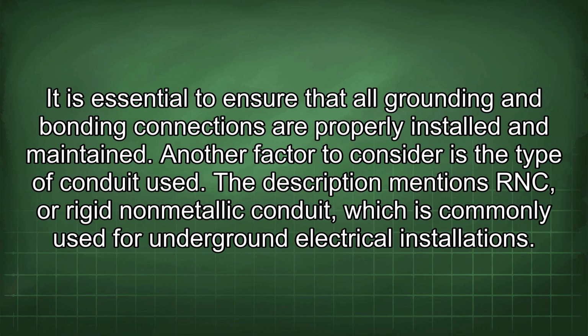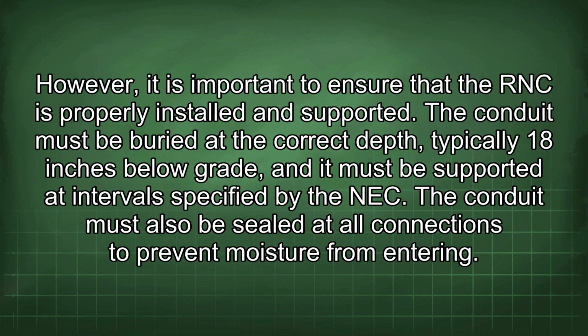Another factor to consider is the type of conduit used. The description mentions RNC, or rigid non-metallic conduit, which is commonly used for underground electrical installations. However, it is important to ensure that the RNC is properly installed and supported. The conduit must be buried at the correct depth, typically 18 inches below grade, and it must be supported at intervals specified by the NEC.